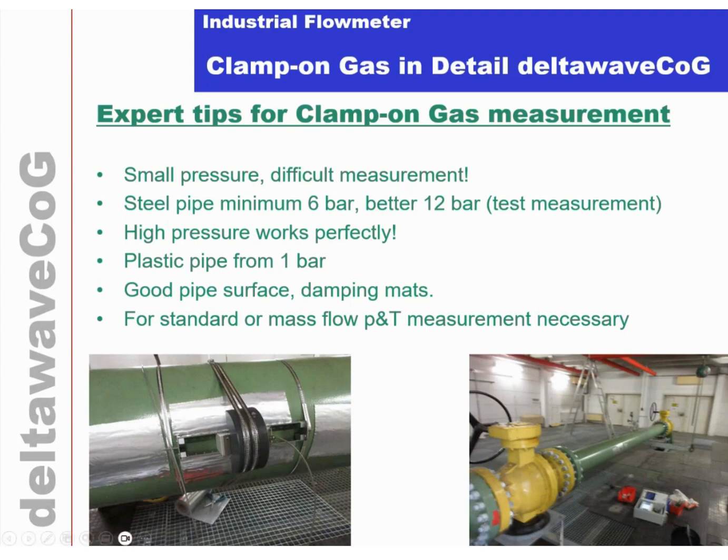So, and here is a perfect application. This is a natural gas pipeline at 40 bars with very low effort. You put it on, after 1 hour you have a perfect measurement, which is in line with the turbine. Very nice measurement. So this is the ideal application.